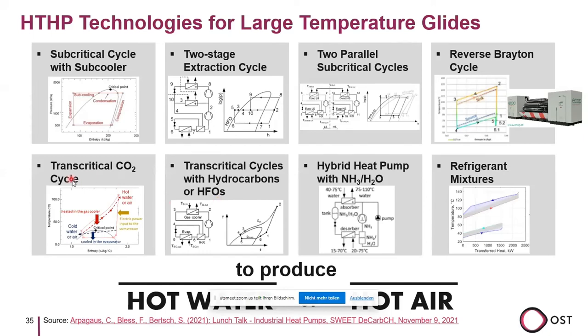Then we have, here's four others, transcritical CO2 cycles. So CO2 has this kind of thermodynamics. Let's say you have a critical point of 31 degrees, so the source has to be lower than that. And then it is very useful to heat up water to 90 degrees, for example, or to make hot water.